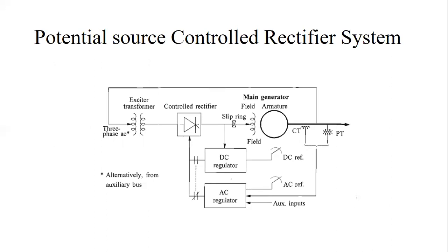This type of excitation system is also commonly known as a bus fed or transformer fed static system. The system has a very small inherent time constant. The maximum exciter output voltage is however dependent on the input AC voltage. Hence, during system fault conditions causing depressed generator terminal voltage, the available exciter output voltage is reduced.